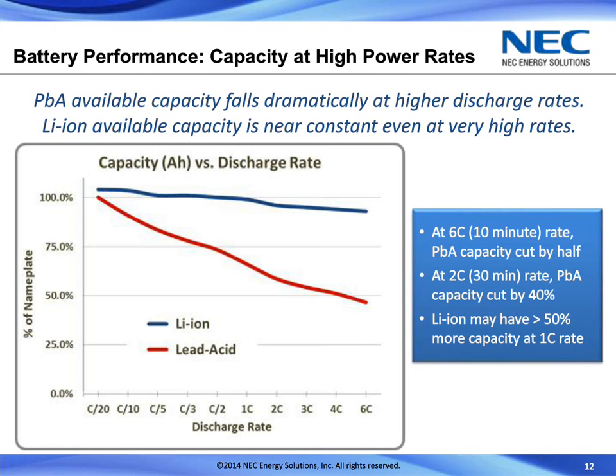Lithium-ion batteries, on the other hand, have a pretty much flat capacity versus discharge rate, meaning they can deliver the same capacity relatively independent of the actual discharge rate. So at high C rates, at high power levels, a lithium-ion battery might have twice as much usable capacity, twice as much available capacity at higher power rates than lead-acid would. And this is actually a pretty important criteria for many applications that are out there.